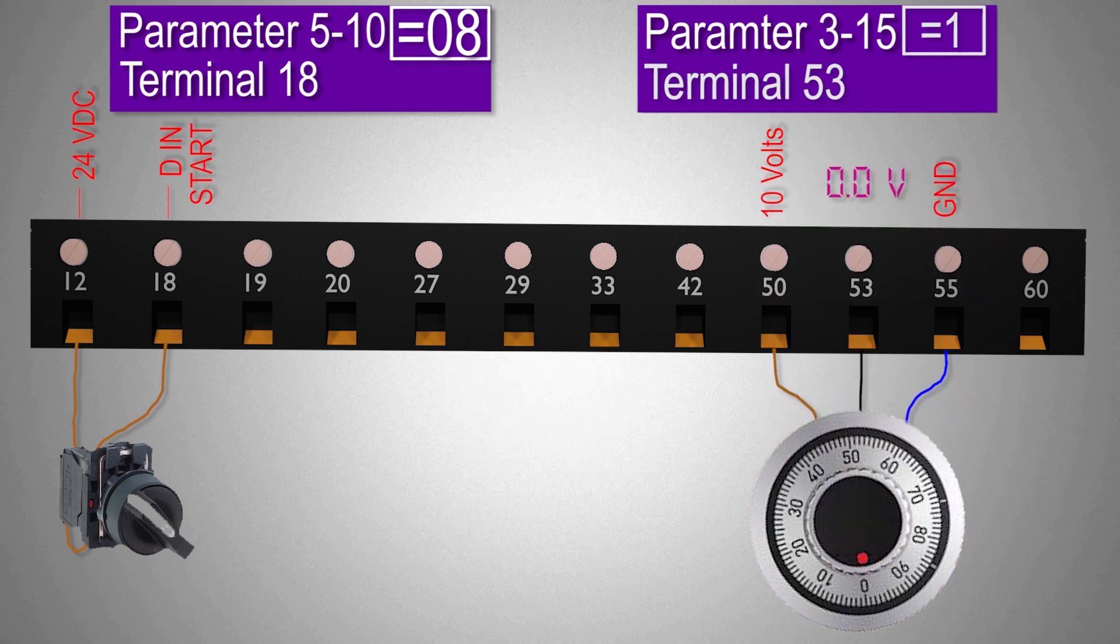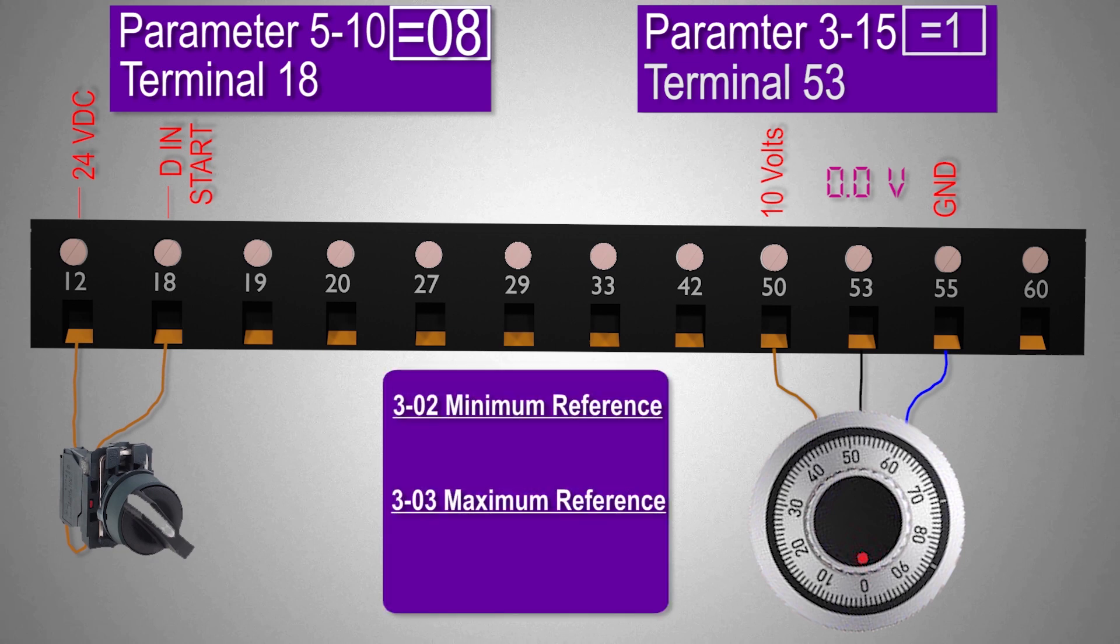There are two other parameters which I want to discuss here are the minimum and the maximum reference which are 3-2 and 3-3 parameters. These two parameters define the minimum speed of the motor at 0 volt analog input signal and maximum speed at 10 volts analog input signal.